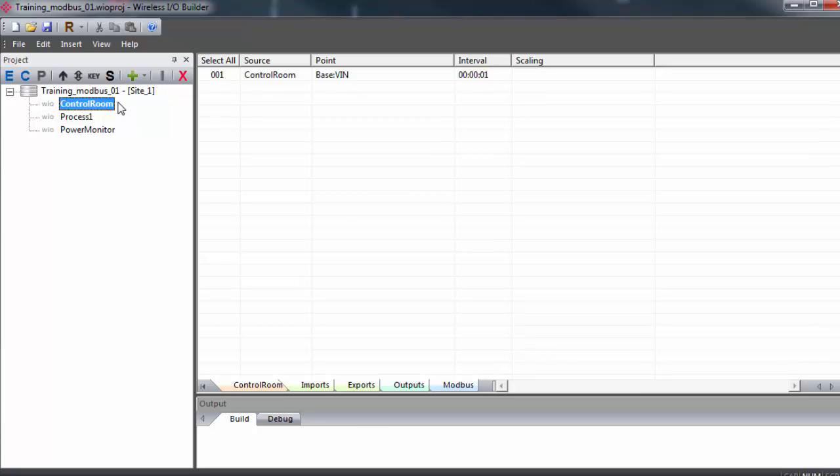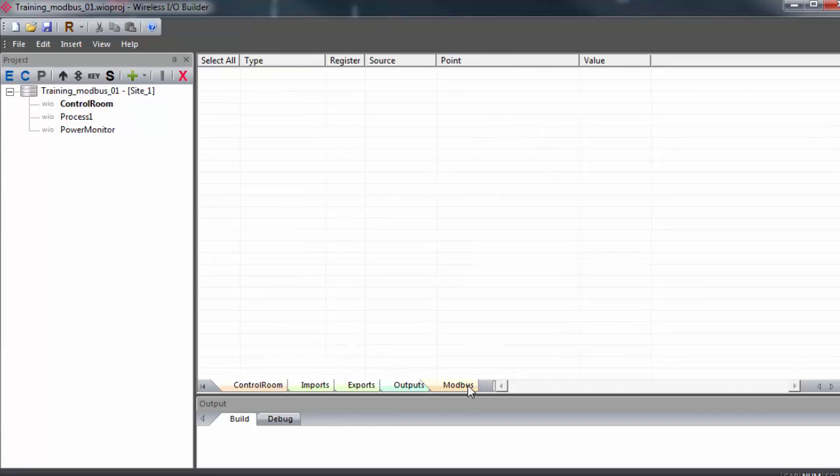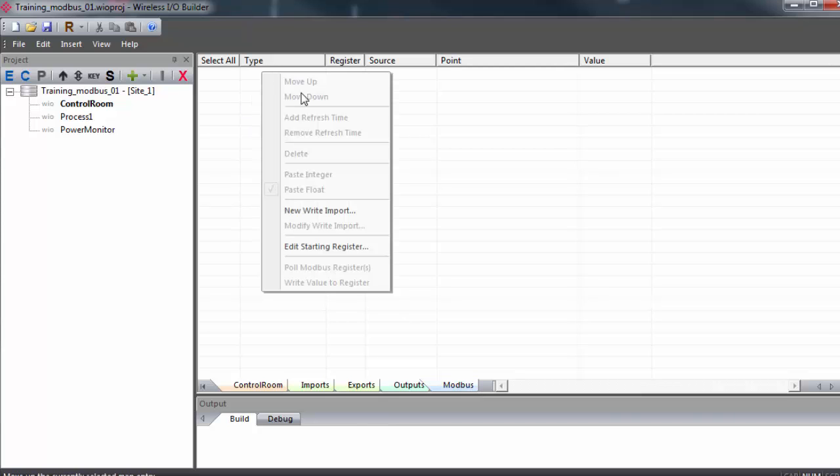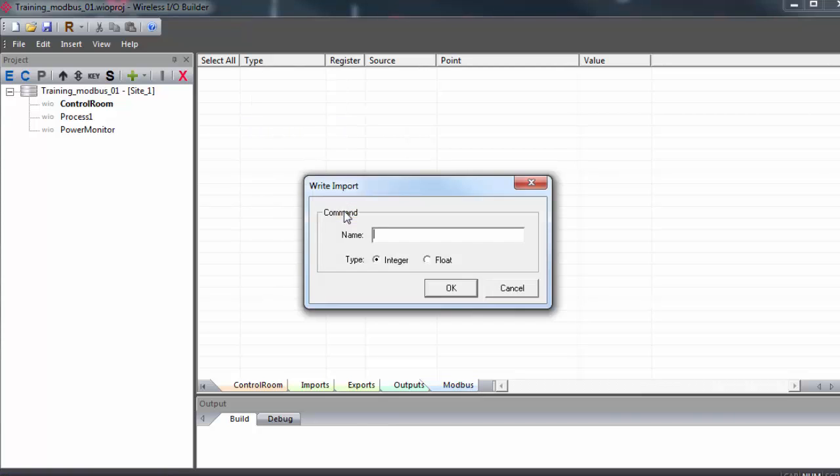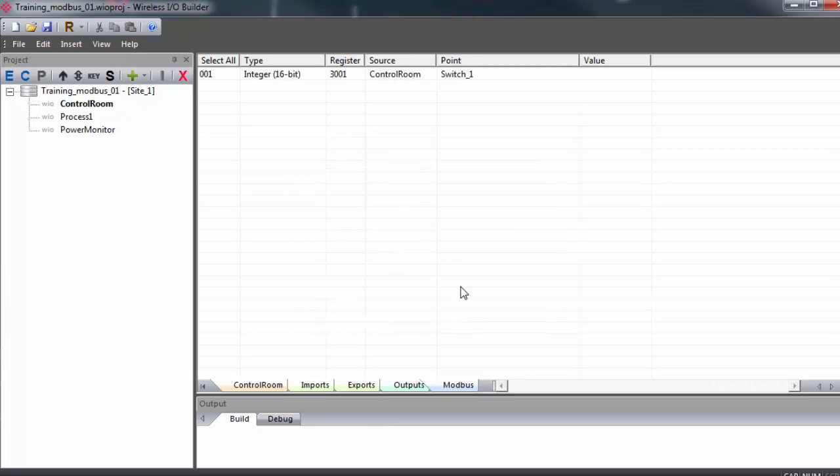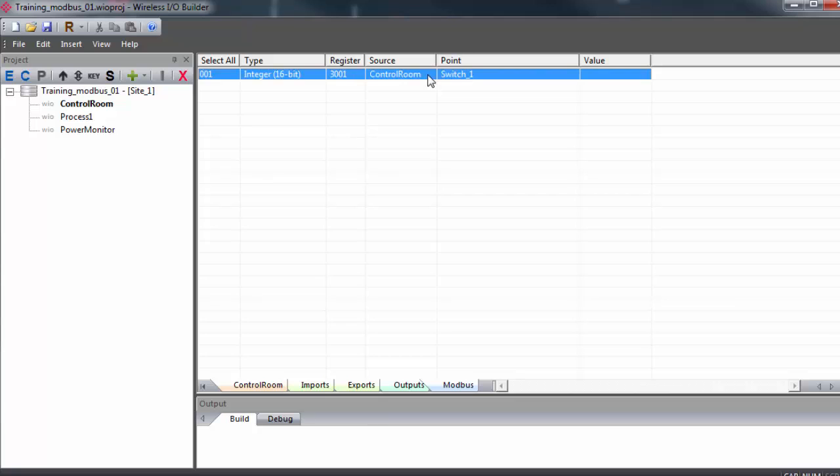Double click on the primary gateway in the project tree and select the Modbus tab. Then in the window, right click and select New Write Import. We'll give a name to our write command. We'll keep integer as the type and click OK. And here we can see our command type integer register 3001. This is the default starting address for integers in the multipoint gateway. Floats start at 7001.